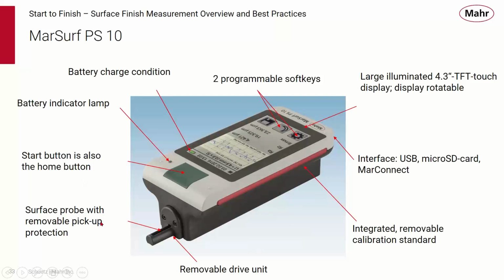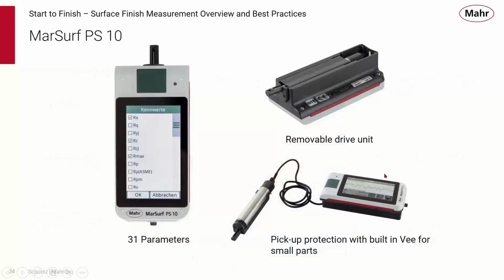A surface probe, which allows for removal, but it also has a pickup protection device. The whole drive system is removable to put into separate fixtures. It has an integrated removable calibration standard, and it has interfaces for USB. You can store the measurements on a micro SD card, and it can use Mahr Connect for our MarCom software. So the PS10 has 31 parameter capabilities. You can see we can drag the screen down with the touchscreen to select by touching the parameters that we want. It has a removable drive unit. Normally the drive is held within the system, but you can take it out with its built-in probe protection and then mount the drive in a stand or use the drive independently in a small bore on the machine.